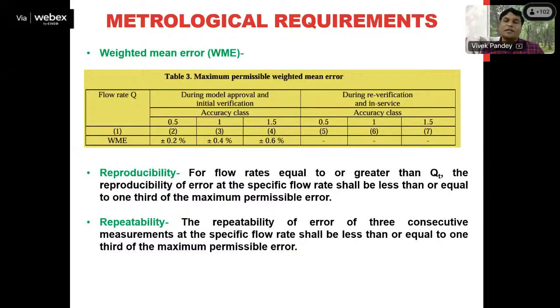Now suppose that gas meter is being checked for its consistency, and we have decided that we will check it at a fixed flow rate of 200 liter per hour. So within 100 to 500 liter per hour, I have decided on a particular flow rate, 200 liter per hour, to check whether at that flow rate its result is consistent enough or not. Okay, so how will we check it? At 200 liter per hour flow rate, we will make a transaction through that gas meter one time, then a second time, then third, then fourth, then fifth. We will take multiple readings.